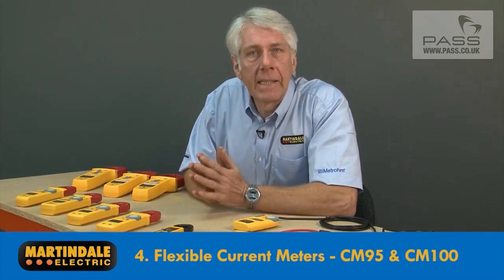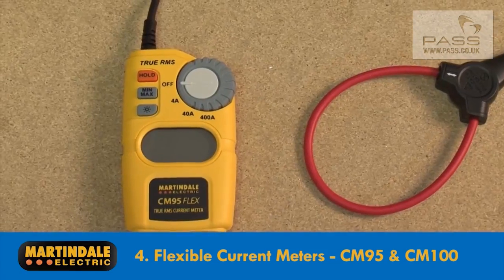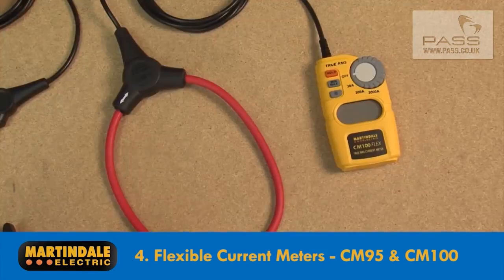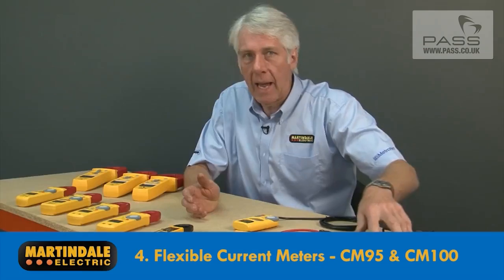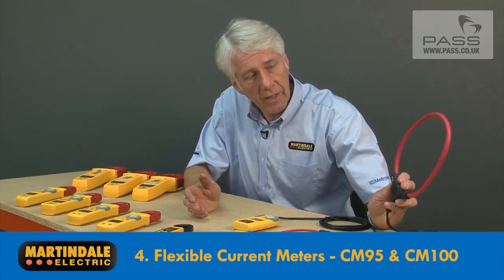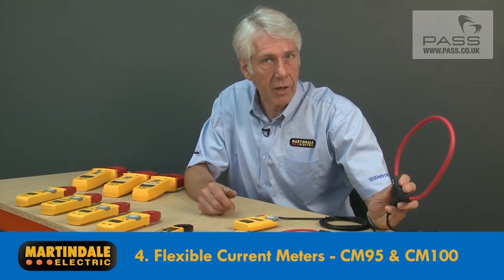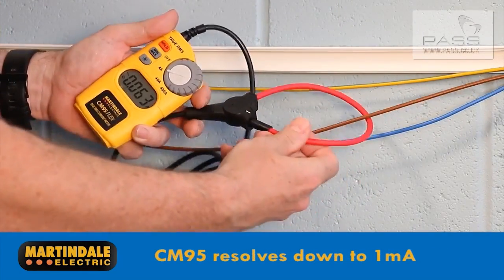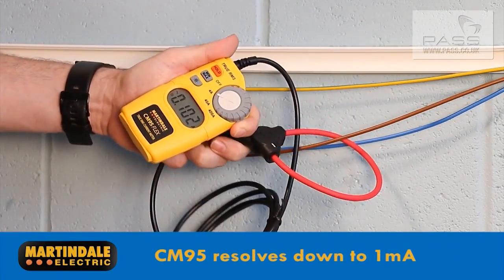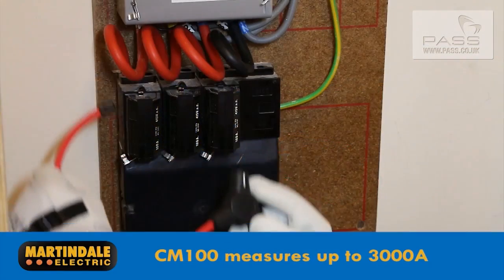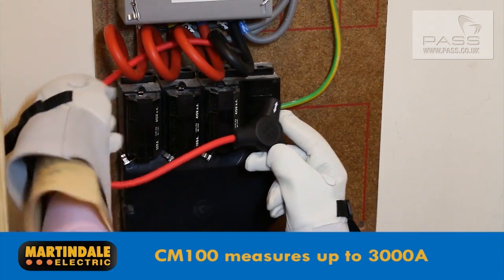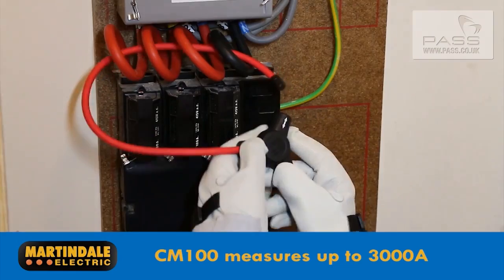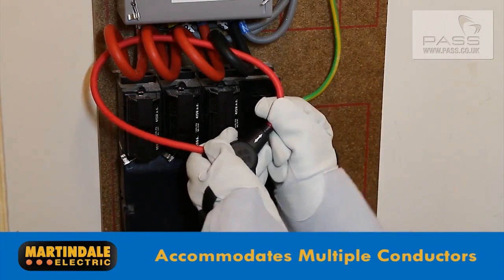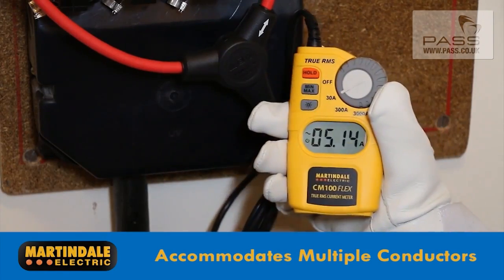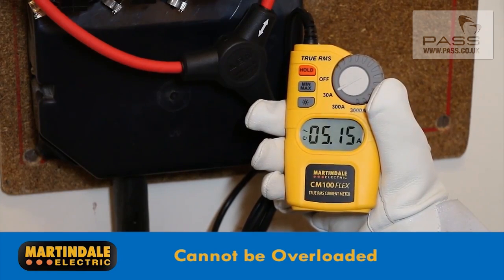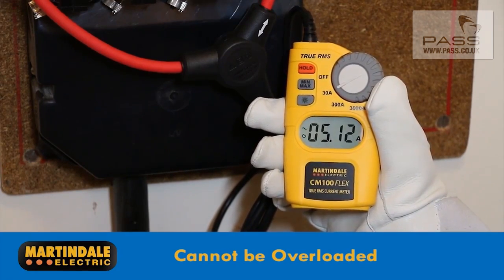The fourth category is lightweight, flexible current meters, such as the CM95 and CM100, enabling access to difficult-to-reach and large conductors where conventional clamps just can't go. The smaller flex of the CM95 will resolve down to 1 milliamp, whereas the large diameter flex of the CM100 will measure up to 3000 amps. And both, of course, can be used around multiple conductors for leakage current investigation. In contrast to conventional CTs, they cannot be overloaded.